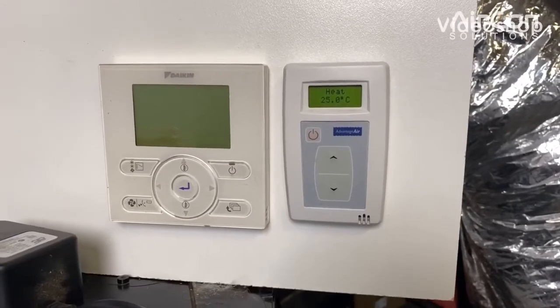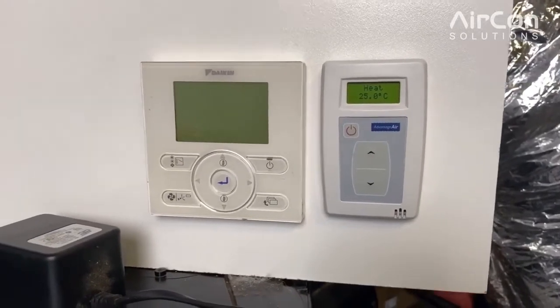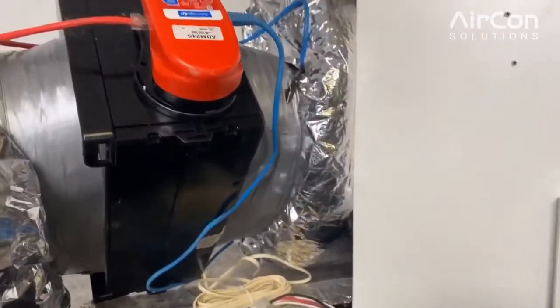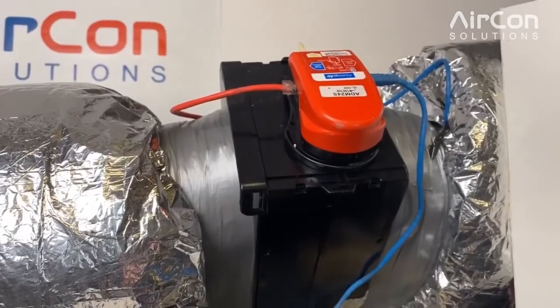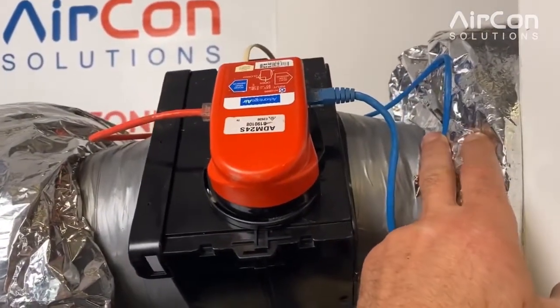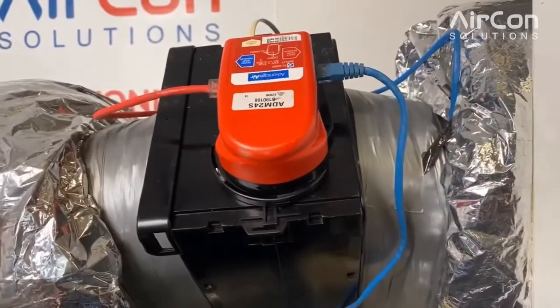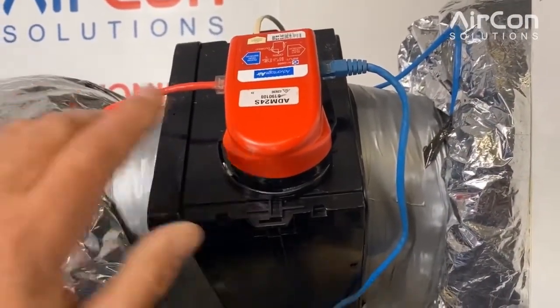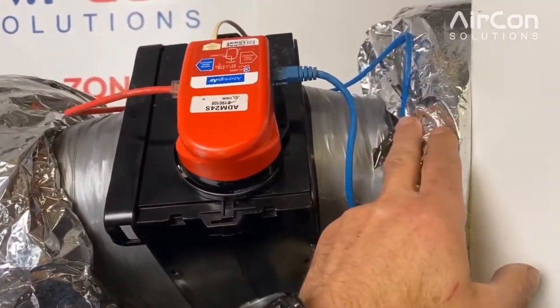In this video we're going to talk about the common issues with the single VAV zone system. We have the zone motor installed. One of the common issues is that installers put the supply air sensor downstream of the zone motor from the unit. We always need to have the supply air sensor installed upstream.